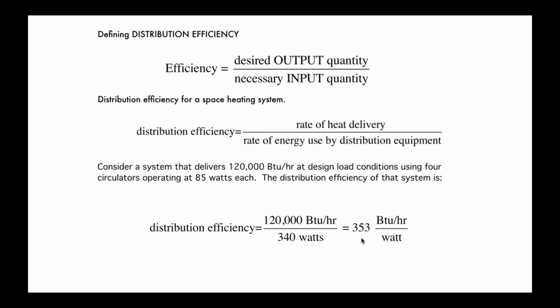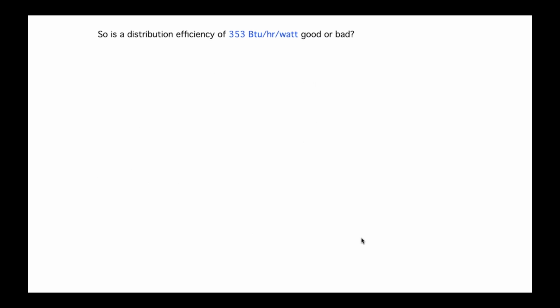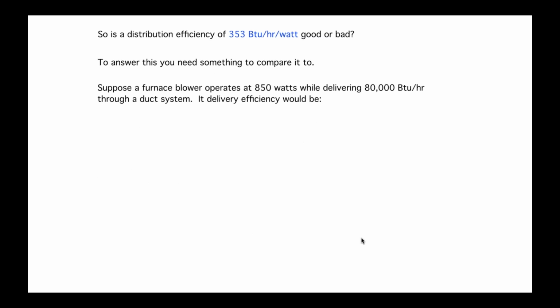Okay. Now, the next question is, is that good? Is it bad? Or is it kind of middle of the road? But you don't have anything to compare it to. All right, so we've got to come up with a comparison. So I'll take an example of an older furnace with, again, a permanent split capacitor type or shaded pole motor, not the most efficient motor technology compared to today's ECMs.